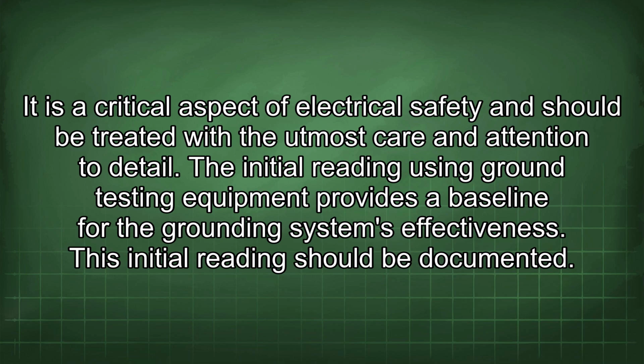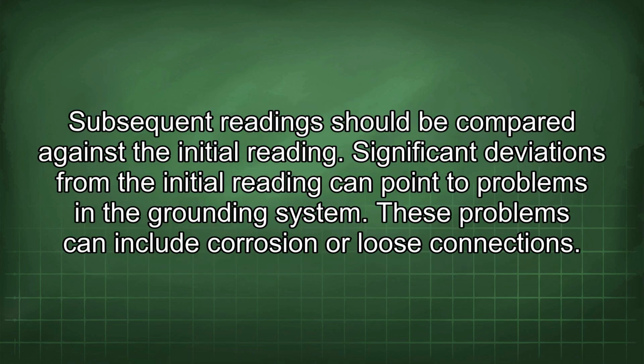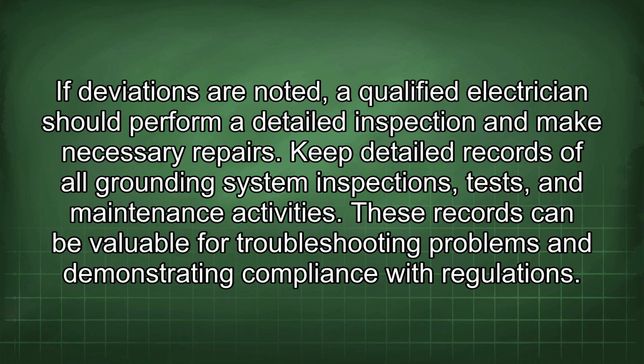This initial reading should be documented. Subsequent readings should be compared against the initial reading. Significant deviations from the initial reading can point to problems in the grounding system. These problems can include corrosion or loose connections. If deviations are noted, a qualified electrician should perform a detailed inspection and make necessary repairs.